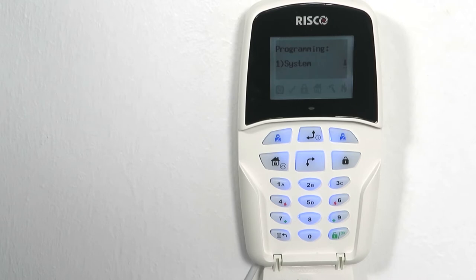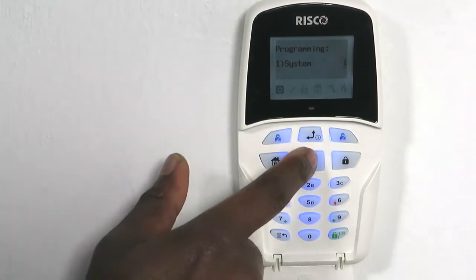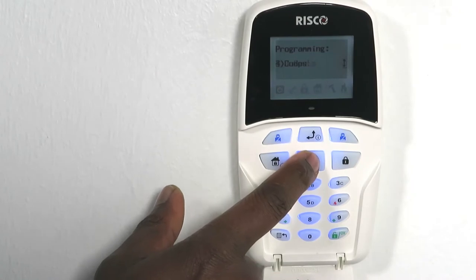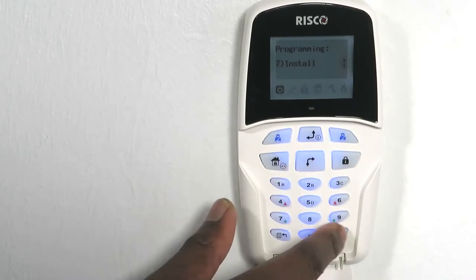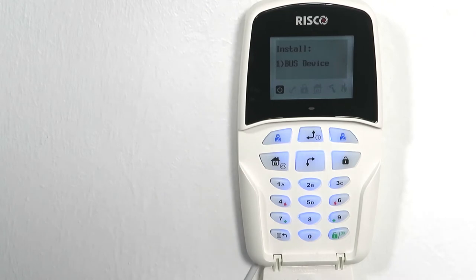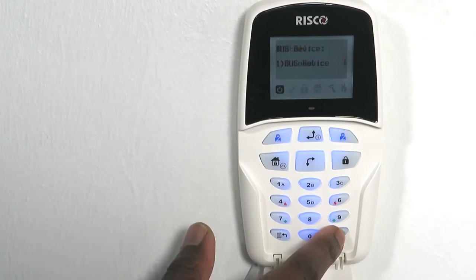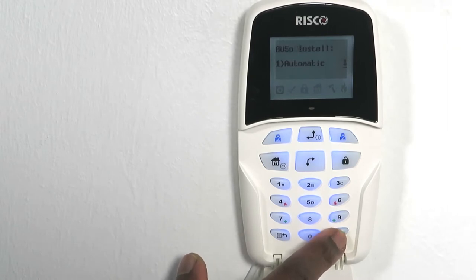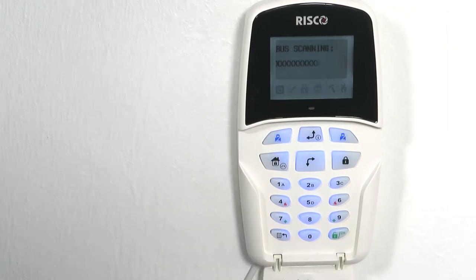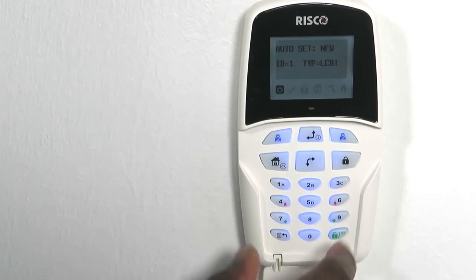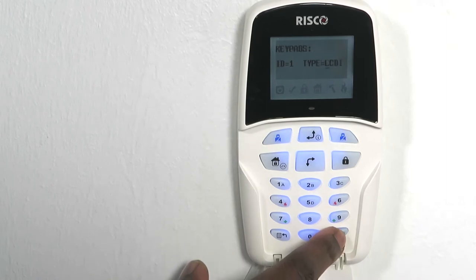The next step is to allocate key bus devices. In the programming menu, scroll to Install and press OK. Press OK to select bus device and then press OK again to select automatic. This will run the automatic bus allocation to make sure that the keypad works correctly after the upcoming reboot. Press OK to confirm the bus devices until you reach the bus device menu again.